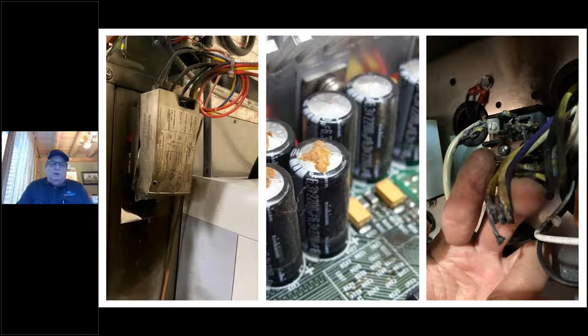Here are some examples of power problems we have seen. On the far left is a soft start that took a nasty hit. The center picture shows part of the inverter drive with damage — a light brown material on top of the capacitors that have blown from a power surge or power strike. These things can benefit greatly from our compressor defender. The soft starts took a lot of beatings until we found the compressor defender, which has resulted in big savings.